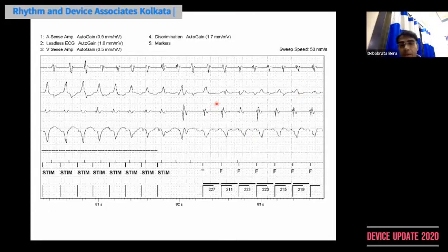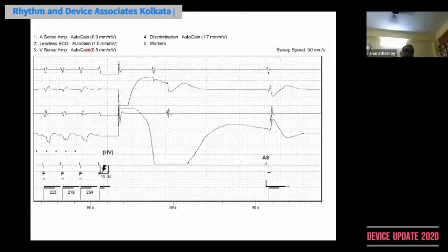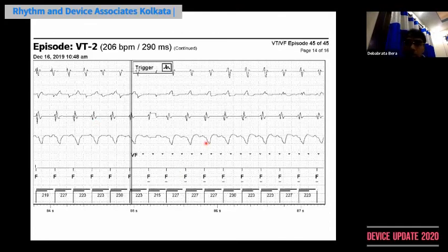So most likely, we are not 100% sure, but 90% this patient developed a true ventricular tachycardia after an ATP, and then it goes faster and enters the VF zone. That's why it is called VF, and the VF triggers a shock. Why did it not give an ATP during charging? Because the device is intelligent. It saw that the last time it delivered ATP, the VT became faster. So this time when VF was detected, no ATP during charging, and a shock was given directly.